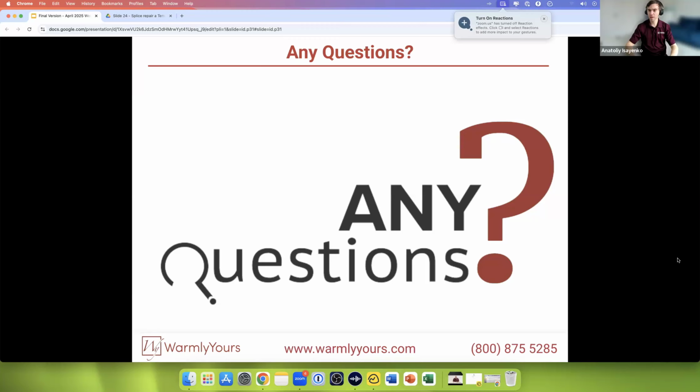Yeah, I agree with all that, and I would say if we potentially suspect a breaker and it's a relatively simple and quick thing to just replace, after you go through all of these steps that we kind of covered now, definitely go ahead and try to replace a breaker. There might be a 1 in 1,000 defective breaker that maybe went in here and that's what's happening. But also, I kind of have that connection to that nuisance, like Scott was mentioning earlier.